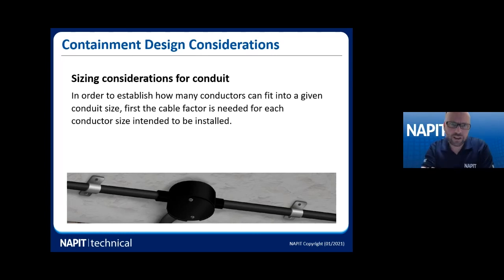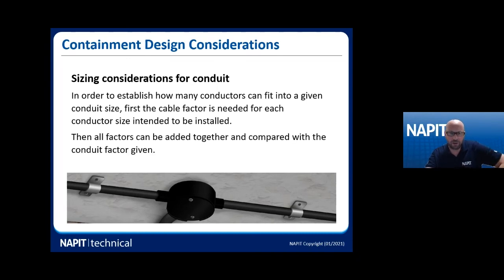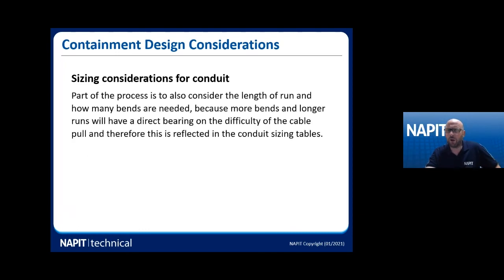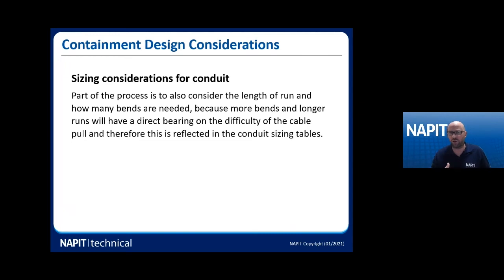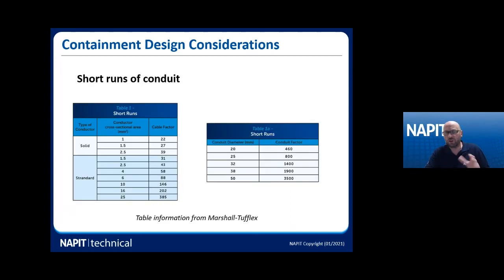Now looking at sizing considerations for conduit. In order to establish how many conductors can fit in, you need the cable factors for each conductor size — it's very similar to trunking. You add all the factors together and compare them with the conduit factor. Part of the process is to consider the length of run and how many bends are needed. The more bends and the longer the run, the more difficult the cable pull — more distance, more bends means more friction — and the tables reflect that.